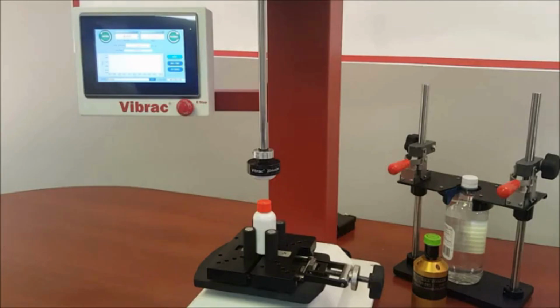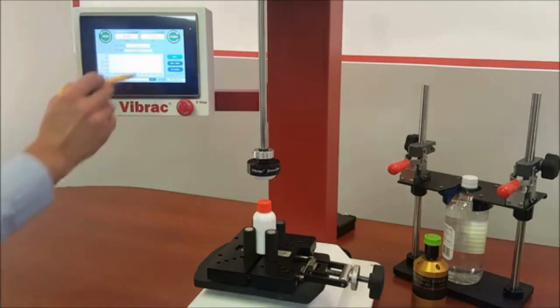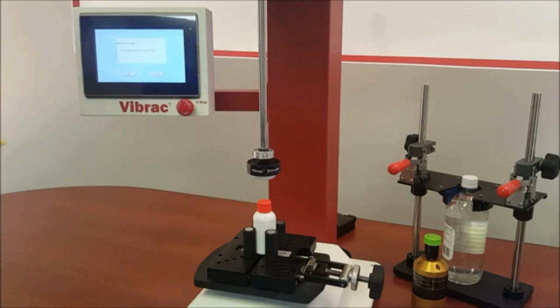Before starting the test, zero the machine by pressing the 0 button. Press 0 again. It is important to remember that the chuck cannot be engaged to the cap while zeroing. After zeroing, engage the chuck to the cap.